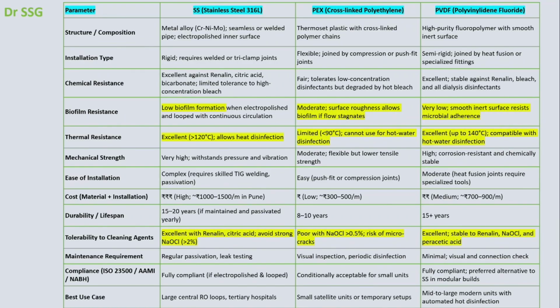Yes, sir, I was coming to that, because some units have 304 also. Absolutely. So 316 is the grade of stainless steel which is recommended, 316 and 316L, because it has molybdenum in 2 to 2.5%, which makes it more corrosion resistant, and it is the recommended material to be used for the distribution system. Then we also have cross-linked polyethylene, that's PEX, which is also widely available, though less useful. And we do have PVDF, which I don't think many units use here in Pune.